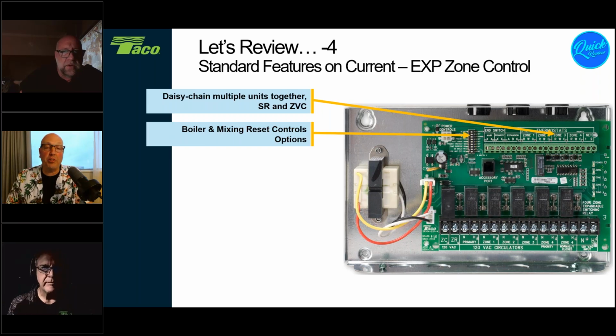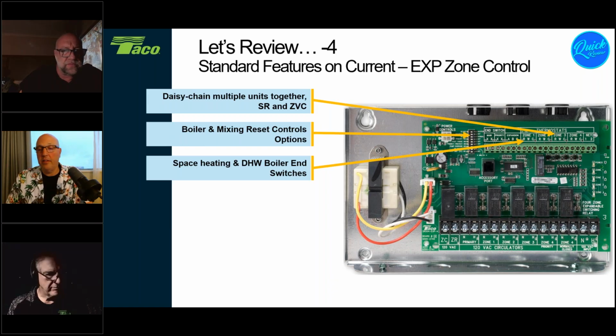We also had components on here, and I just noticed something happened to my image here. It's a little askew. The expansion terminal is located right here. The arrow's in the wrong spot. This arrow should be right here where it says power controls. So the boiler and mix set reset controls, we had an add-on controller called the PC 700, 702, 705 that would plug into that terminal that could give us some extra functionality. But it was an option that you can add. We have the DHW terminal. We have our main end switch tying into our boiler for CH. And then we had our priority terminal to our boilers that had a second terminal for an input to tell it to fire.